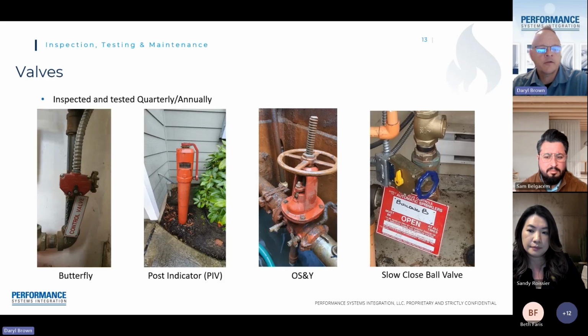Some of the other components on a fire sprinkler system, these are the basic components. As I stated before, a fire sprinkler system takes water to operate. These are the main valves that feed into the sprinkler system. On the left, you see a butterfly valve, a post indicator valve, an OS&Y, and a ball valve. Basically, these are control valves that allow water into the sprinkler system, but also allow you to isolate that sprinkler system in case of maintenance or construction that is happening. These valves are maintained at all times. As you can imagine, if these valves get closed, the fire sprinkler system is inoperable. So these are some of the items that are definitely tested during our quarterly visual inspection and during our annual inspection and test. These are some main components.